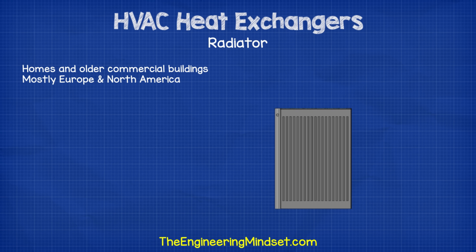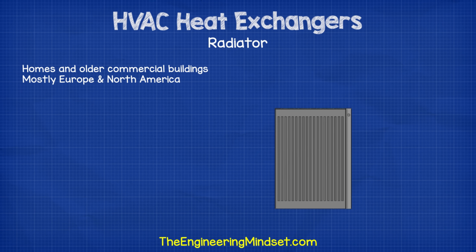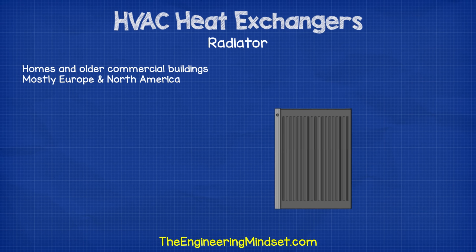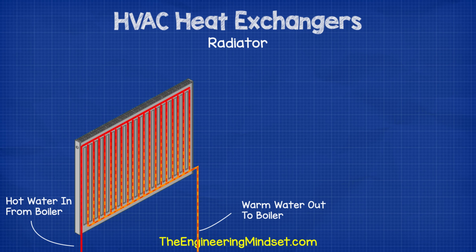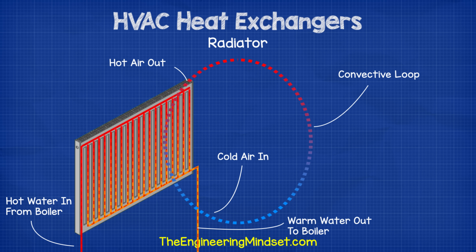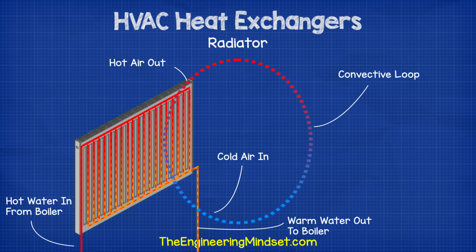Radiators are very common, especially across Europe and North America in homes and older commercial buildings. They are mounted to walls, typically under a window, to provide space heating. They are connected to a hot water pipe fed from a boiler. The internal area of the radiator is larger than the pipe, slowing water velocity and allowing more time for heat transfer. The heat conducts to the metal walls, heats the air on the outside, causing it to rise, and cold air moves in to replace it — this moving air is convection heat transfer.